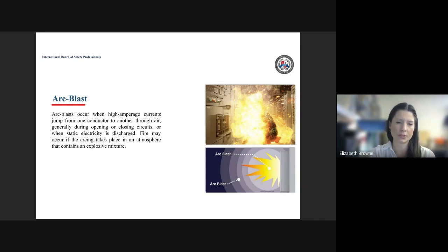These can occur when we're switching. These can occur anytime that the current jumps from one conductor through another through the air. It generally happens when we're opening or closing the circuits, like I meant with switching, and that static electricity gets discharged, which typically seems to be a minor event that we experience when we're walking across carpet in our socks.